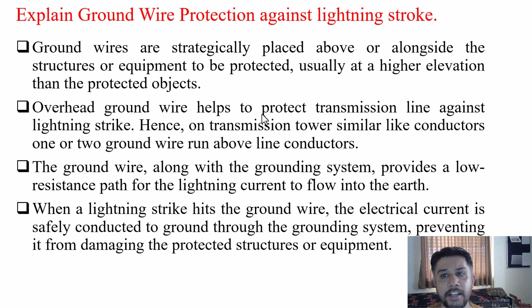The ground wire intercepts lightning strikes, preventing direct hits to the phase conductors, and reduces power outages and equipment damage. By safely directing lightning induced surges to the ground, it helps maintain system stability and prevents insulation breakdown. It provides a low resistance path for fault currents, ensuring rapid fault clearance. It reduces the risk of electrical shocks to maintenance personnel and nearby infrastructure by properly grounding stray currents.